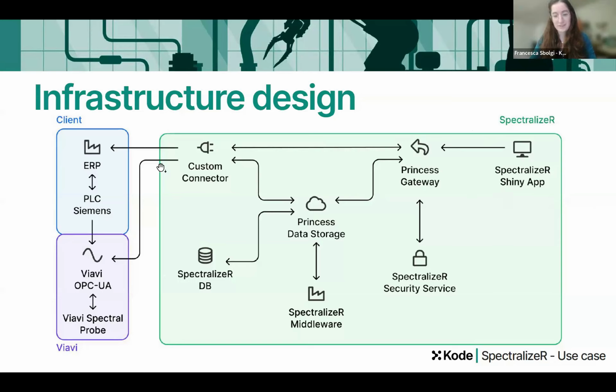What happens in practice is that a bit of sample from the production is automatically diverted into the lab, where a conveyor belt takes the sample under the spectral probe, and they can use the PLC to operate the probe, so to start and stop the acquisition of the spectra. The spectra are then visible on the OPC, and from there we can start collecting the data, storing it, doing some computation, and then finally show the predictions.